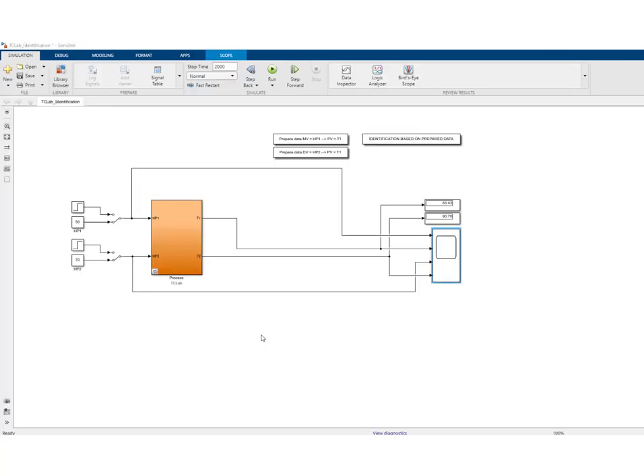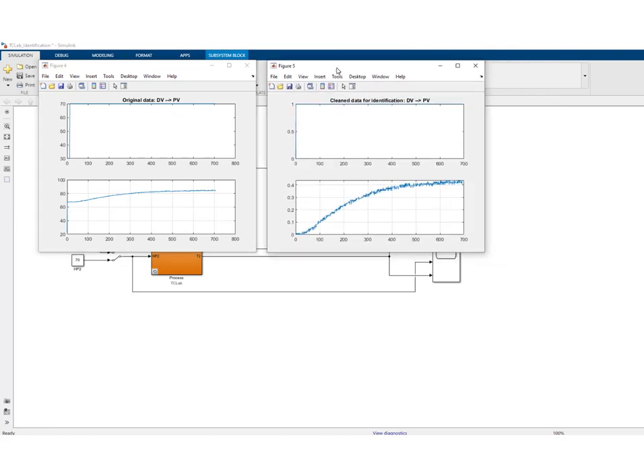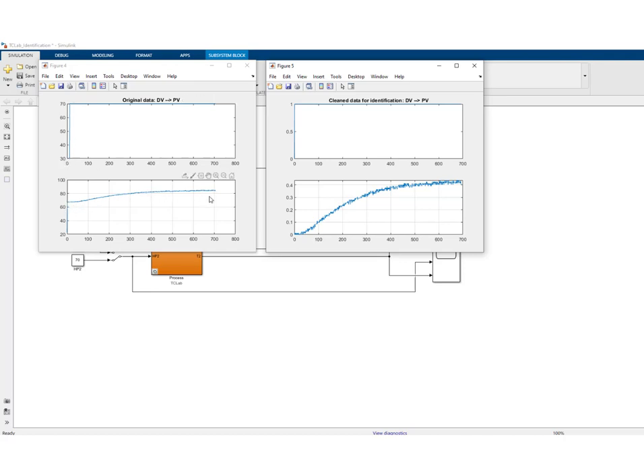We'll now perform the identification procedure again, but this time identifying the disturbance dynamics. We did a step on DV, so we push the second button to prepare data. This shows the original data — a step change of DV from 30% to 70% and the influence on PV — as well as the cleaned data, where everything is brought back to a step change of 1% on DV and its influence in terms of delta PV. Save all these data under PDF format.